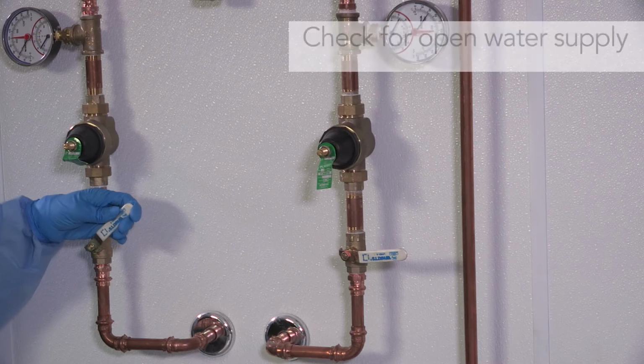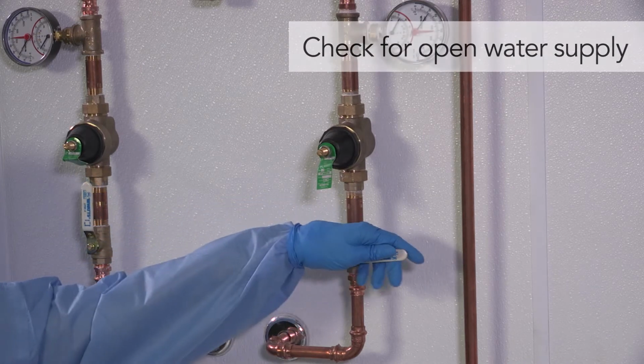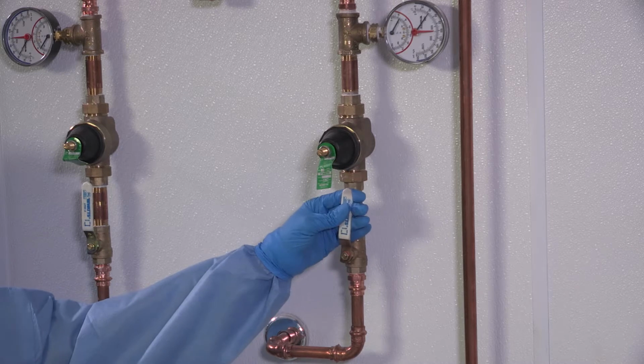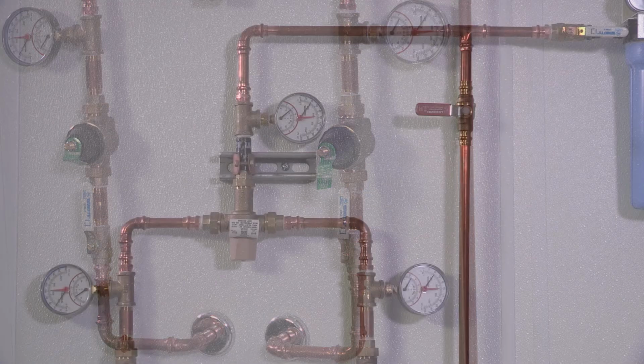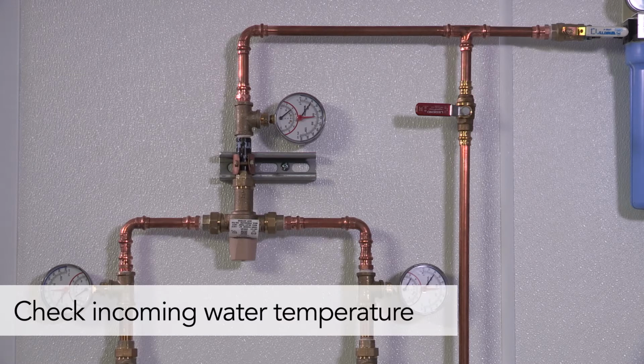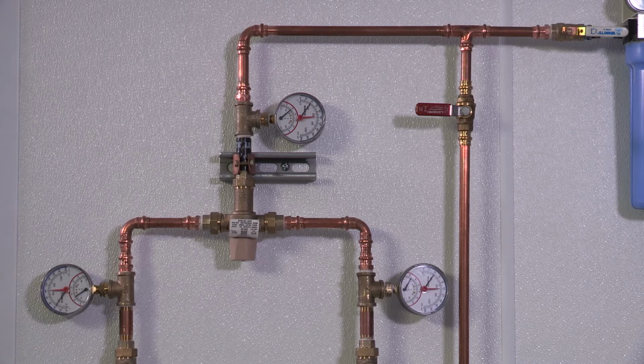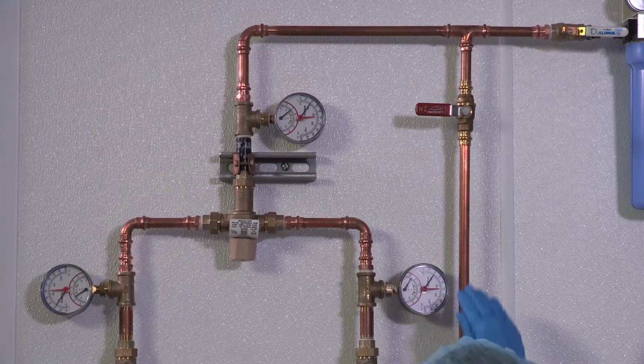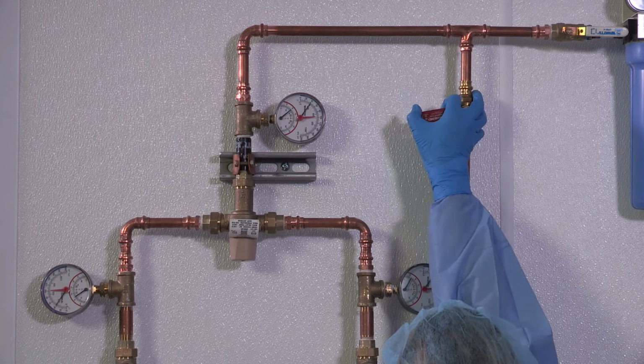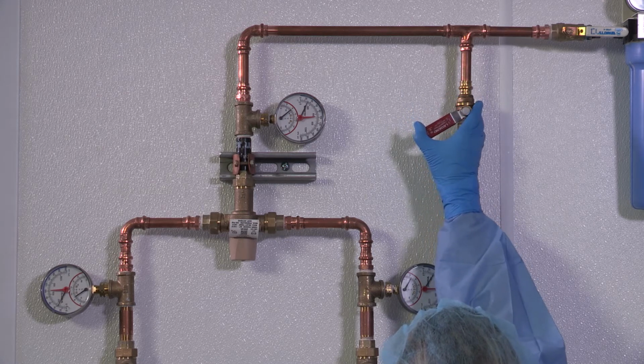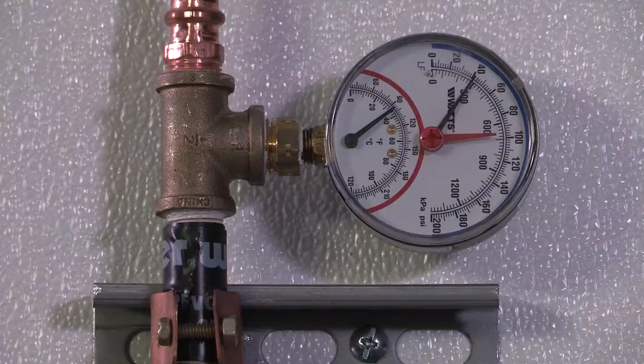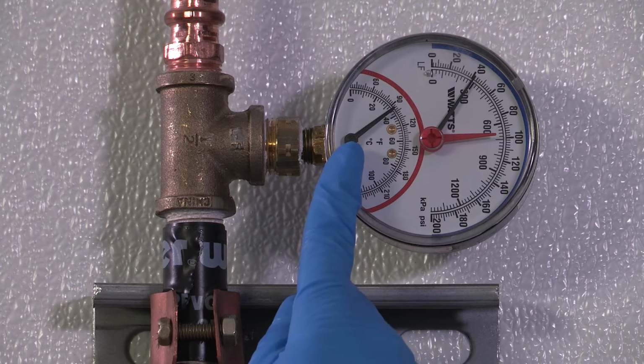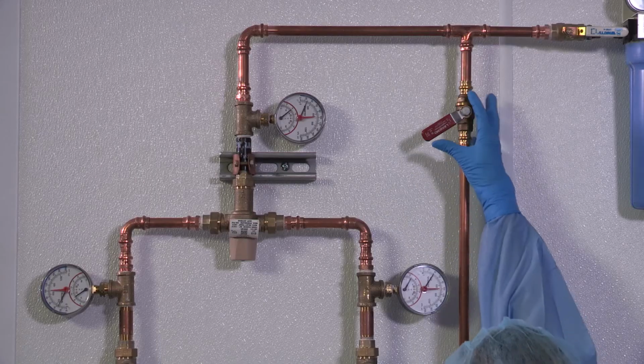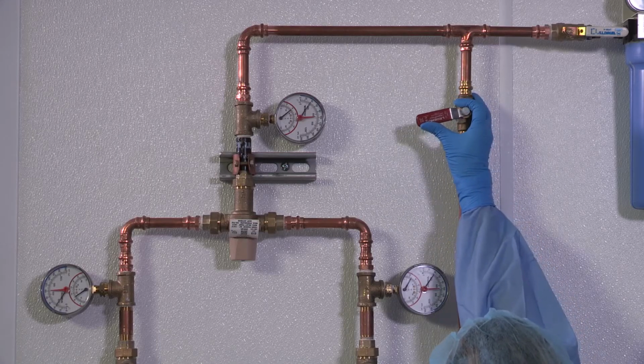Ensure the incoming waterline valve is in the open position. The unit will not operate without water pressure. Confirm the incoming water temperature is within the required operational range of 35 degrees plus or minus 2 degrees Celsius. This can be accomplished in one of two ways. If your reprocessor is plumbed with a bypass valve to send the incoming water down the drain, open the valve. The temperature of the water can be monitored by the inline temperature gauge. Close the valve when the gauge reads approximately 35 degrees Celsius.